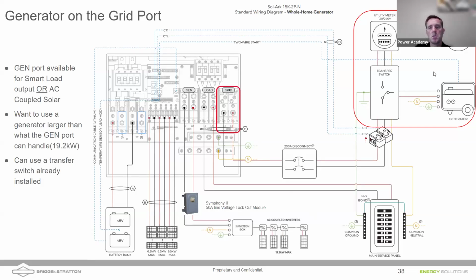So this is a generator we don't expect to do frequent use of, right? Unless it's really rainy or cloudy conditions and the AC coupled solar is not able to charge the battery, well, then the generator could come in. So if you've got long outages, this might be something you want to have as generator backup. And you could also go with a smaller generator here, right, Daniel? Yeah, as long as it's 240. As long as it's 240, good.